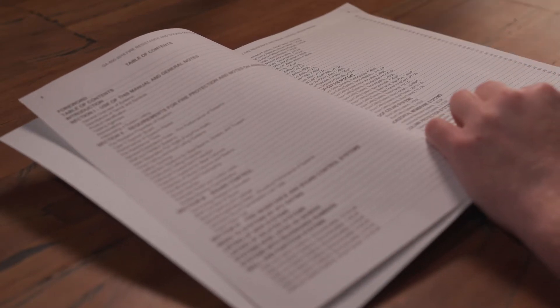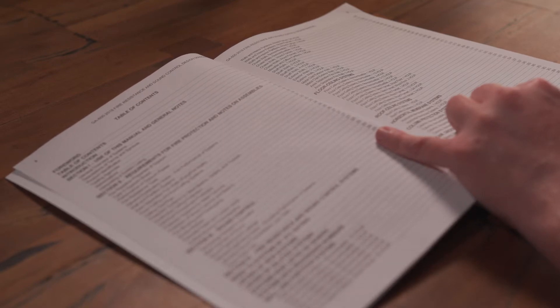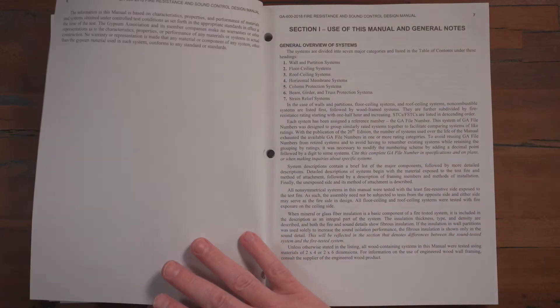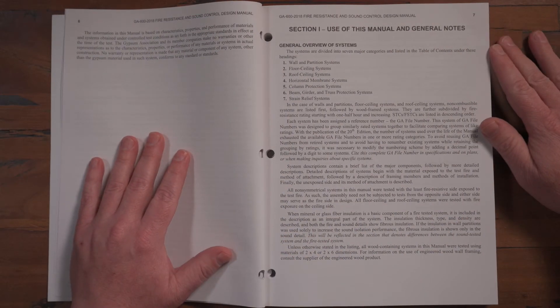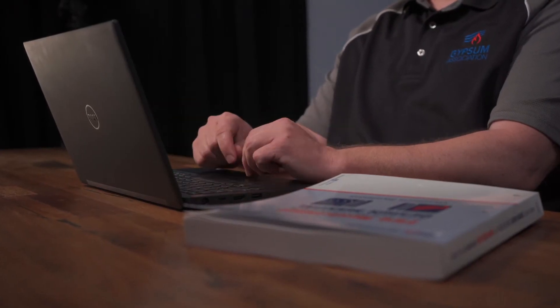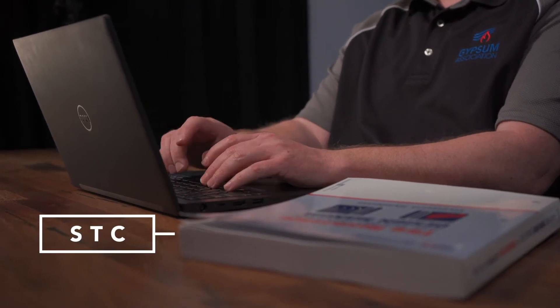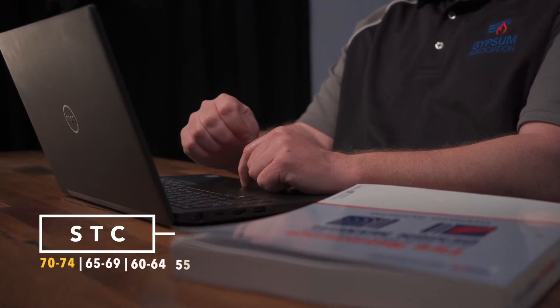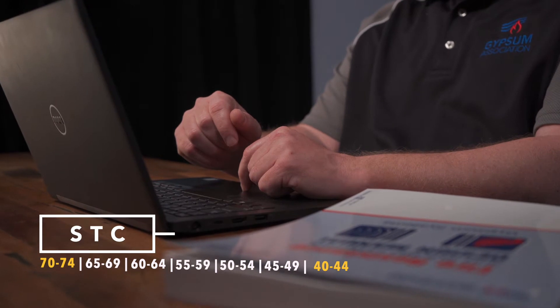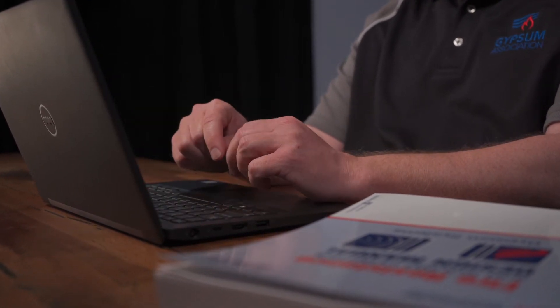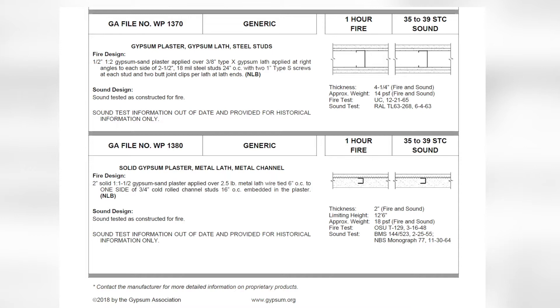Systems are further subdivided by fire resistance rating beginning with one-half hour and increasing to four hours. Walls, partitions, and floor ceiling systems are also classified by sound transmission class, abbreviated as STC. The impact insulation class is included for many floor ceiling systems. STCs are listed in descending order and range from 70 to 74 down to 40 to 44. In GA600 2018, STCs below 40 are excluded because these systems will not meet today's code criteria, though a few are retained for historical reference in renovation or restoration projects, as seen on pages 86 and 87.